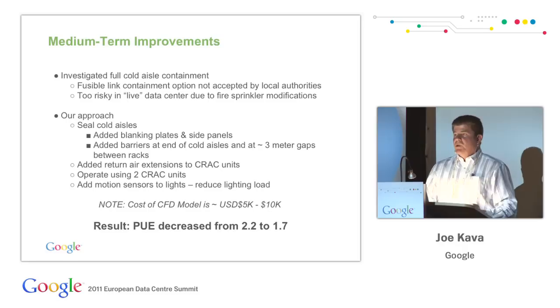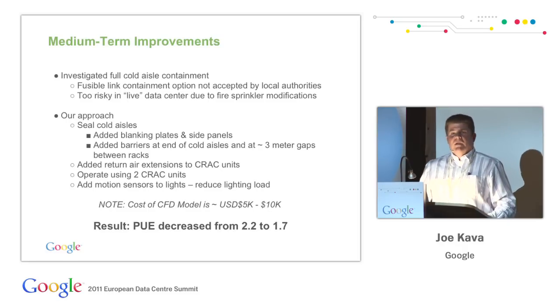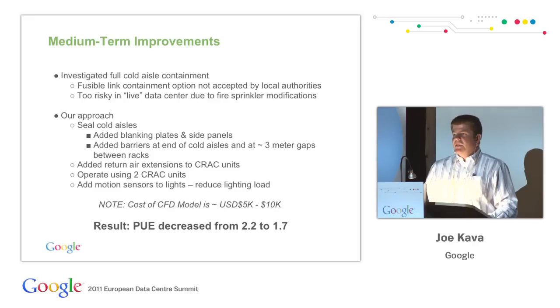And most importantly, we turned down the unneeded cooling. So we turned down the stages of the compressors that weren't needed. And this had a pretty dramatic reduction in the PUE from 2.2 down to 1.7.